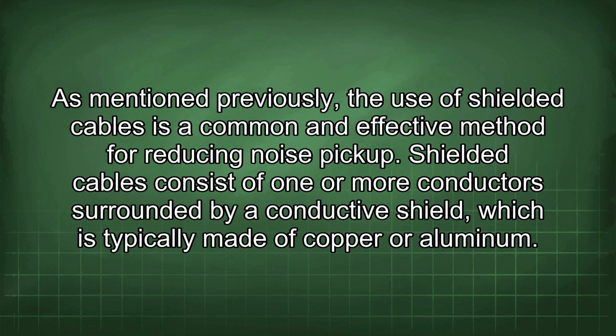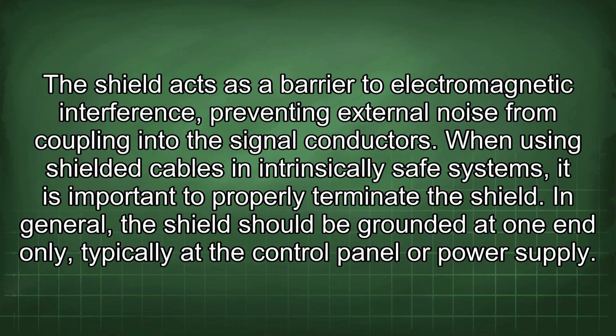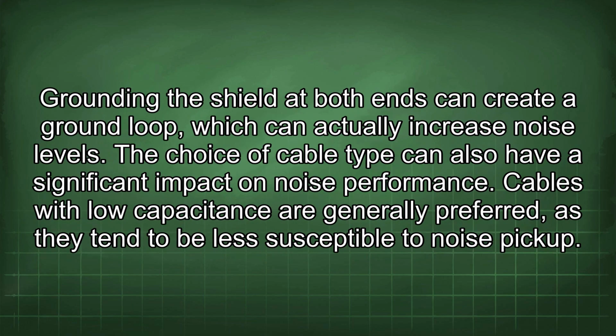As mentioned previously, the use of shielded cables is a common and effective method for reducing noise pickup. Shielded cables consist of one or more conductors surrounded by a conductive shield, which is typically made of copper or aluminum. The shield acts as a barrier to electromagnetic interference, preventing external noise from coupling into the signal conductors. When using shielded cables in intrinsically safe systems, it is important to properly terminate the shield. In general, the shield should be grounded at one end only, typically at the control panel or power supply. Grounding the shield at both ends can create a ground loop, which can actually increase noise levels.